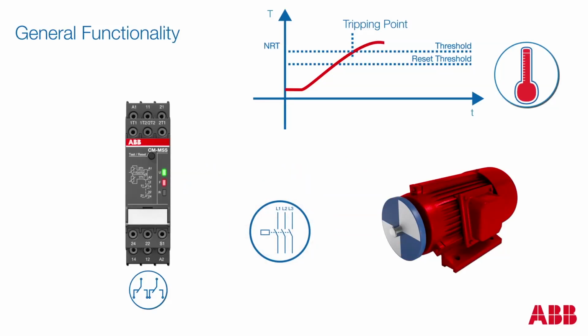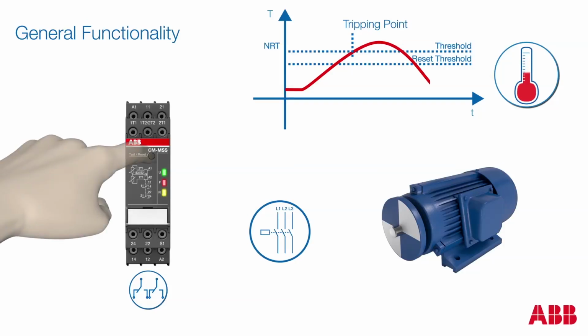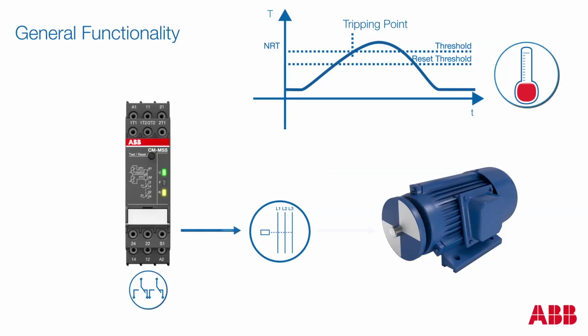As soon as the motor cools down and the temperature reaches the reset threshold, it is possible to reset the thermistor motor protection relay. A reset is possible via the front face reset button, as shown here, remotely by connecting a switch between S1 T2 or automatically by jumpering S1 T2. The yellow LED signals the possibility to reset with blinking with a high frequency. After the reset, the relay closes again, thus triggering the motor contactor to restart the motor.